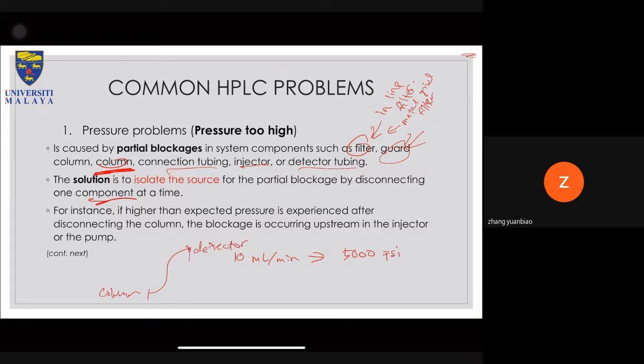So you want to disengage the last tubing going from the column to the detector. Just open that one, put it in a beaker, and run your system at 10 mL per minute. If, say, your pressure goes down to about 4,950 psi, then you can say there might be some impurities in the detector, but this is not the main culprit, especially if your reference run is 2,500.